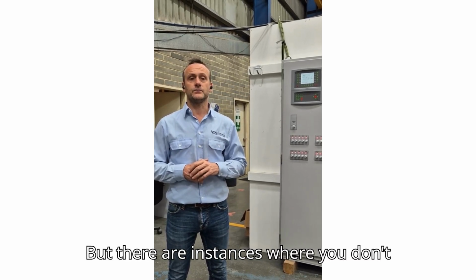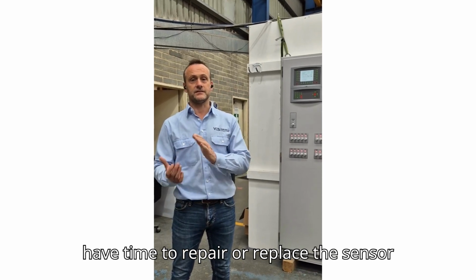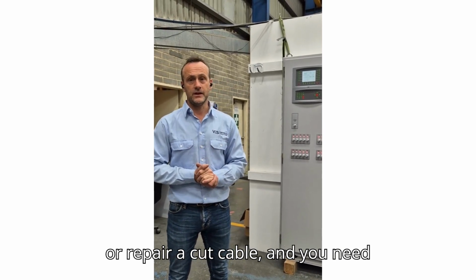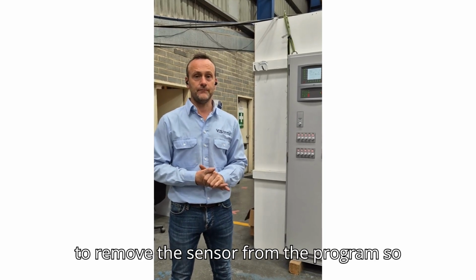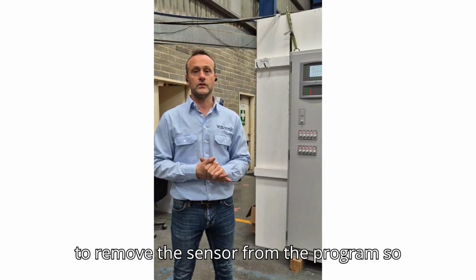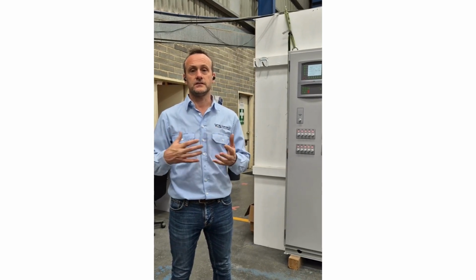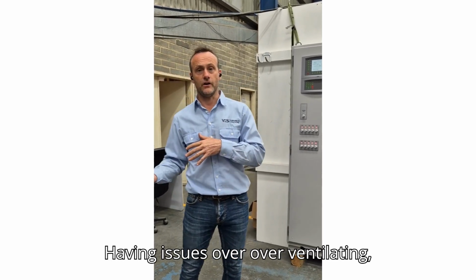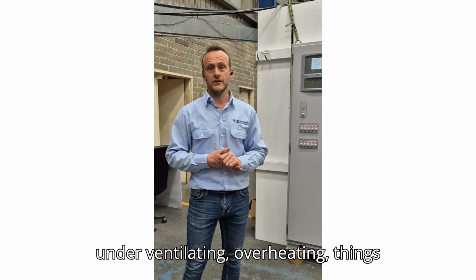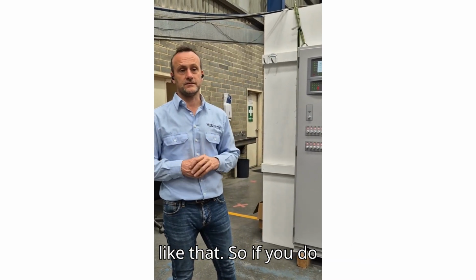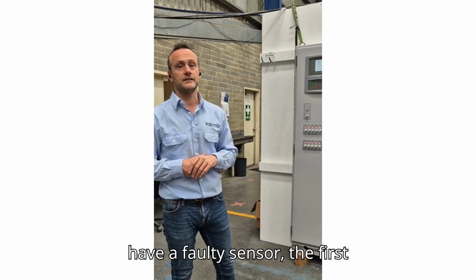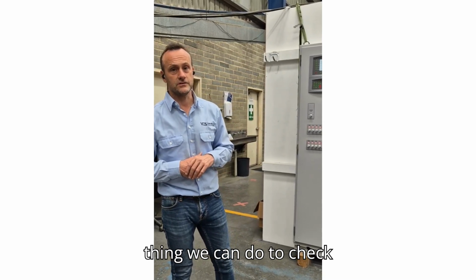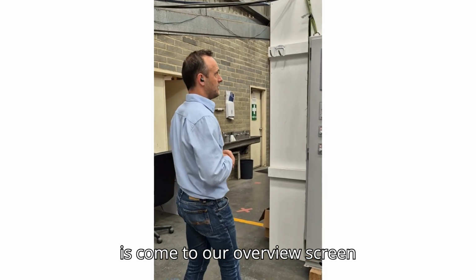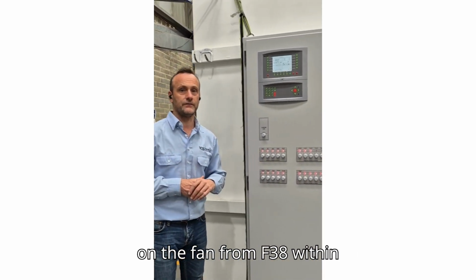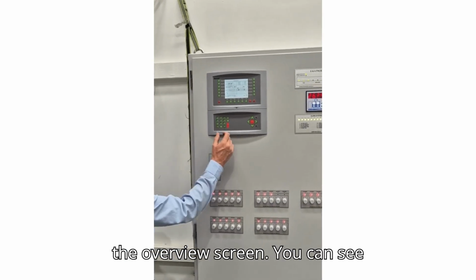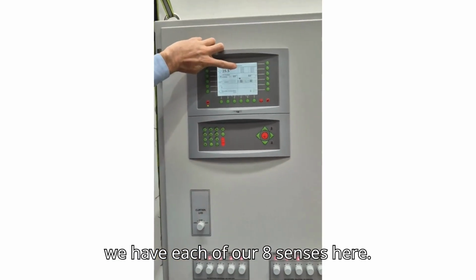but there are instances where you don't have time to repair a sensor, replace a sensor, or repair a cut cable, and you need to remove a sensor from the program so that it doesn't cause your ventilation to have any issues, over-ventilating, under-ventilating, overheating, things like that. So if you do have a faulty sensor, the first thing we can do to check is come to our overview screen on the Fancom F38. Within the overview screen, you can see we have each of our 8 sensors here.